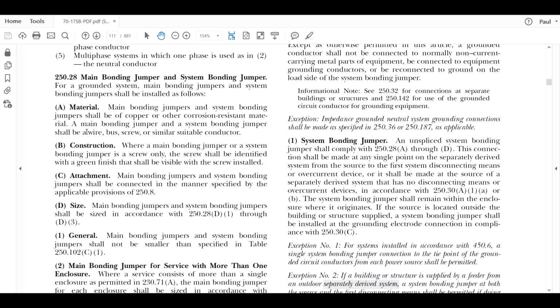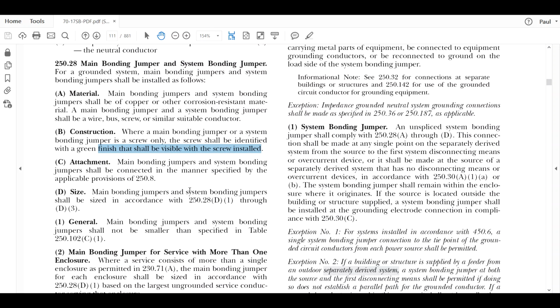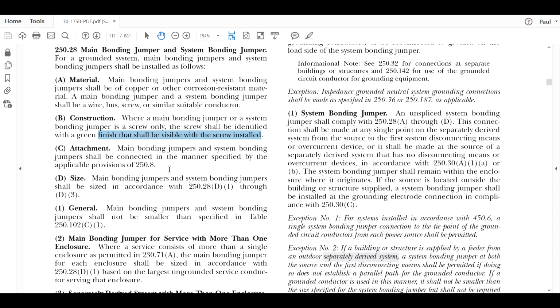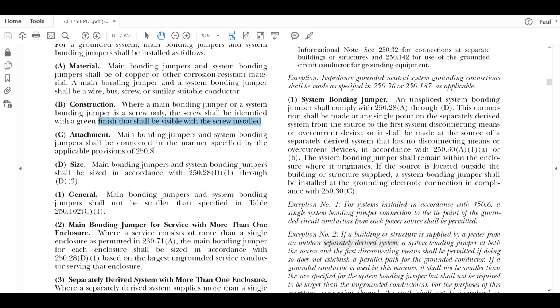In our case, we use the wire. Again, if it's a screw, it has to have a green finish, visible after it's installed, if you want to use that option. We're not, we're using the wire. Now let's get into sizing. 250.8 just gives you all the methods to make the types of connections. So pressure connections and all those types of things are all listed under 250.8. Those are the different types of permitted terminations. Sizing now.